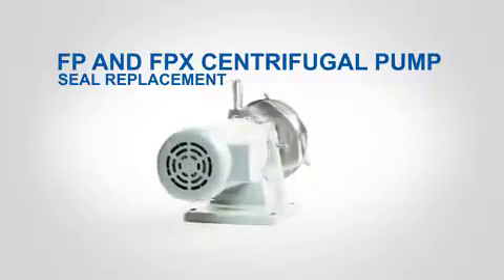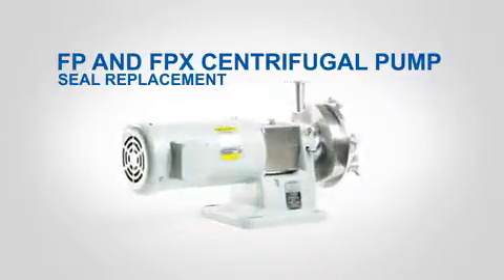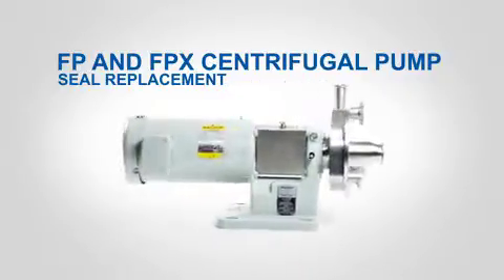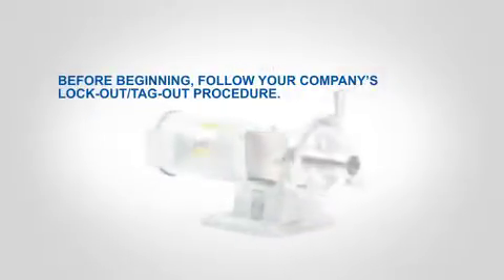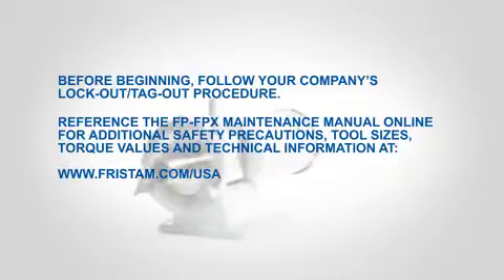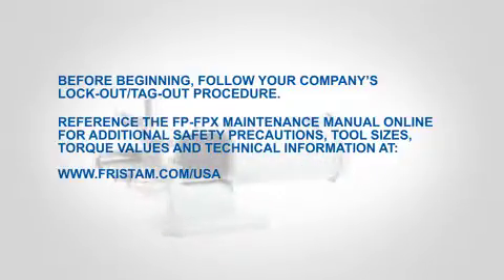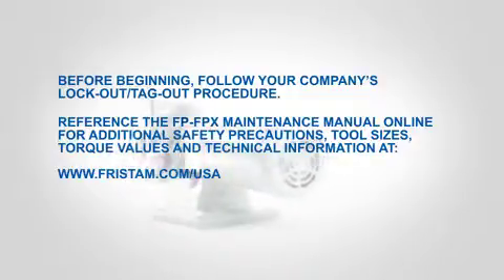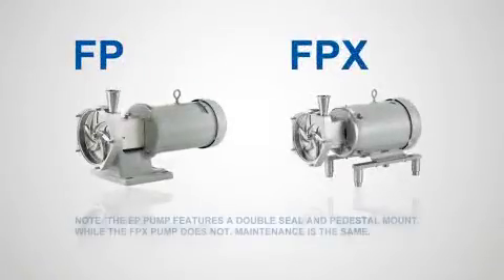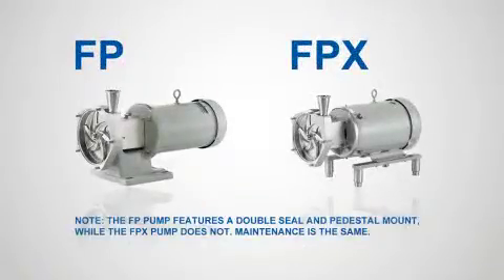FP and FPX centrifugal pump seal replacement. Before beginning, follow your company's lockout, tagout procedure. Reference the FPX maintenance manual online for additional safety precautions, tool sizes, torque values, and technical information. The FP pump features a double seal and pedestal mount, while the FPX pump does not. The maintenance is the same.